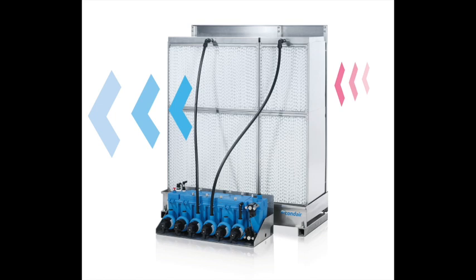So evaporative or spray humidifiers operating in the winter inside an AHU will need some form of heating before the humidifier. Now this makes the air warm enough to be able to accept moisture from the humidifier, and also ensures it's at the correct supply temperature after the evaporative cooling effect. Okay, so how about energy? With the need for buildings to be more sustainable and the high cost of energy, how does energy consumption influence humidifier system design?